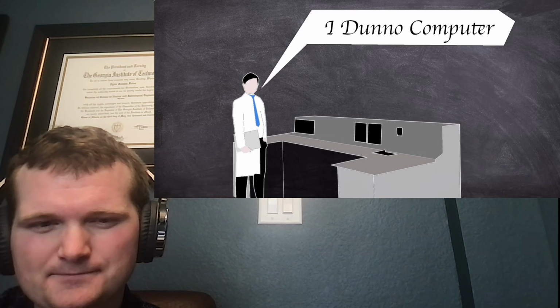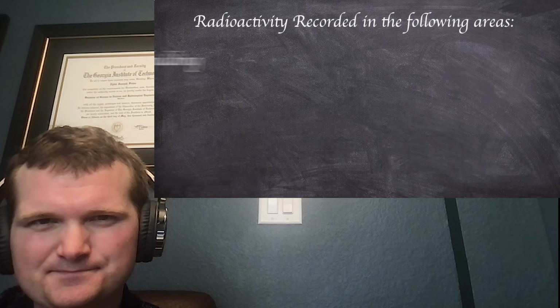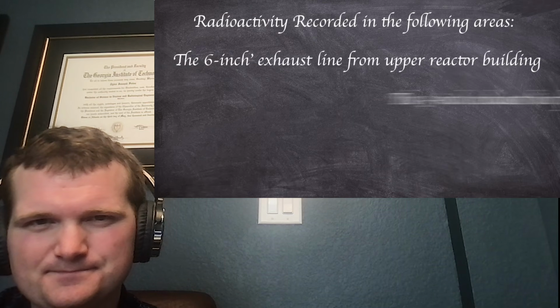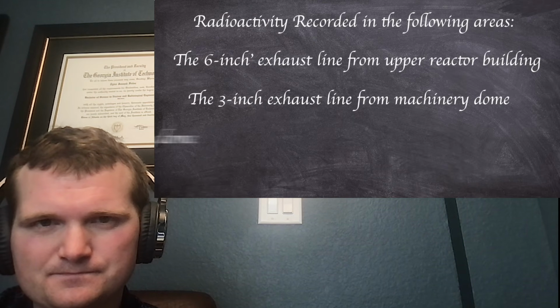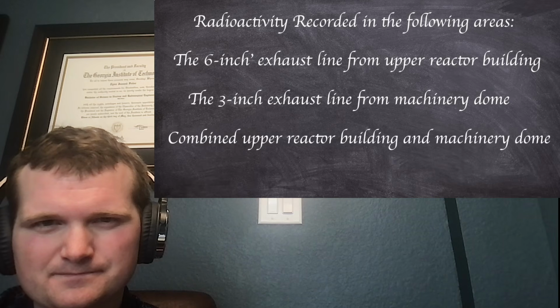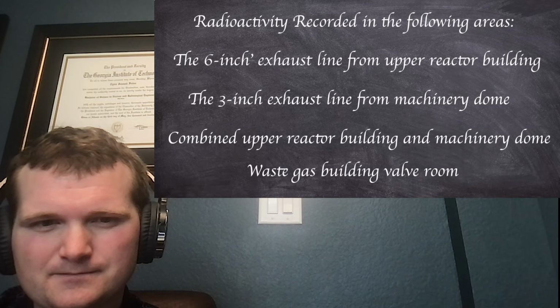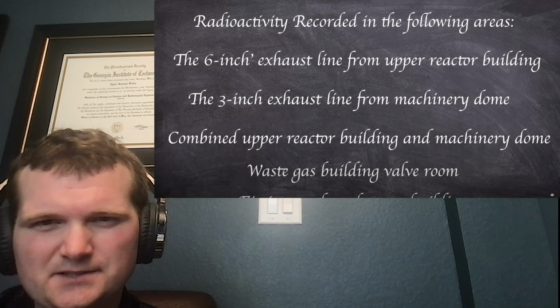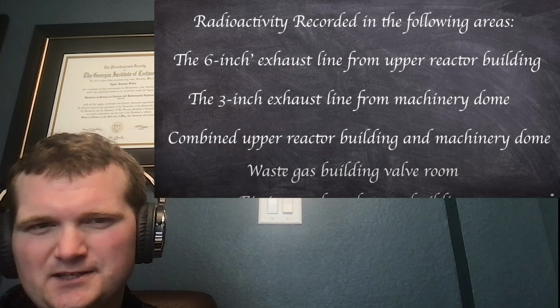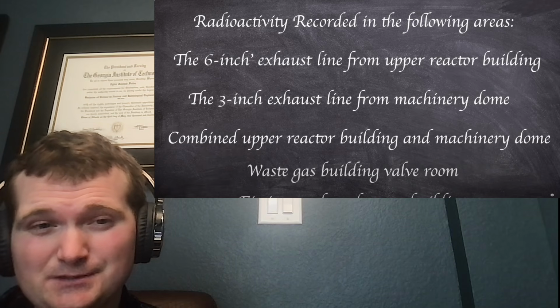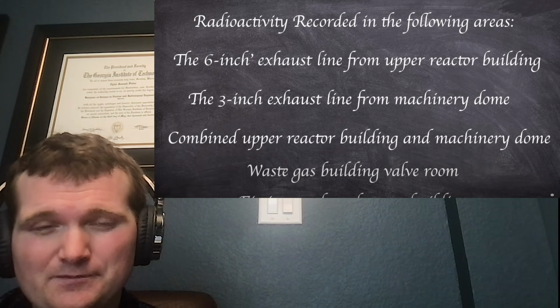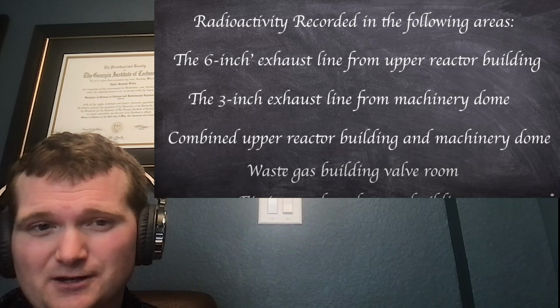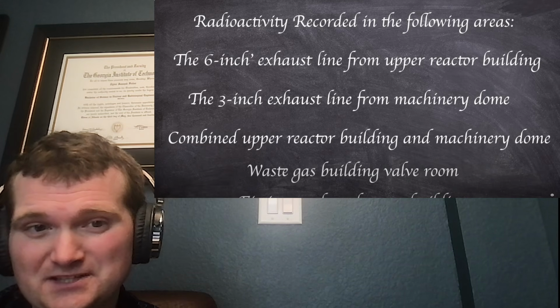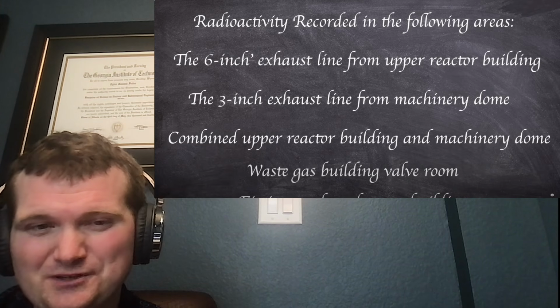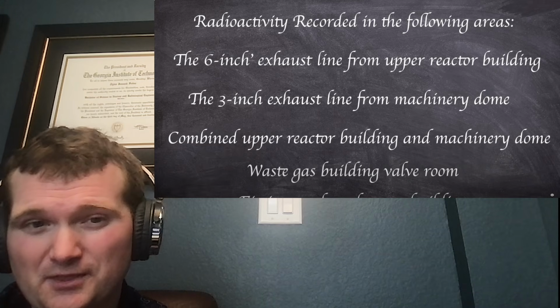Elevated radiation was recorded in the following areas: the 6-inch exhaust line from the upper reactor building, the 3-inch exhaust line from the machinery dome, upper reactor building and machinery dome exhaust, the waste gas building valve room, and the fission product detector building. So yes, high radiation in the reactor containment building is one of the first indicators reactor operators are trained on, that, hey, there's a leak somewhere, because after all, it should be well contained within the reactor vessel, within the reactor coolant system.